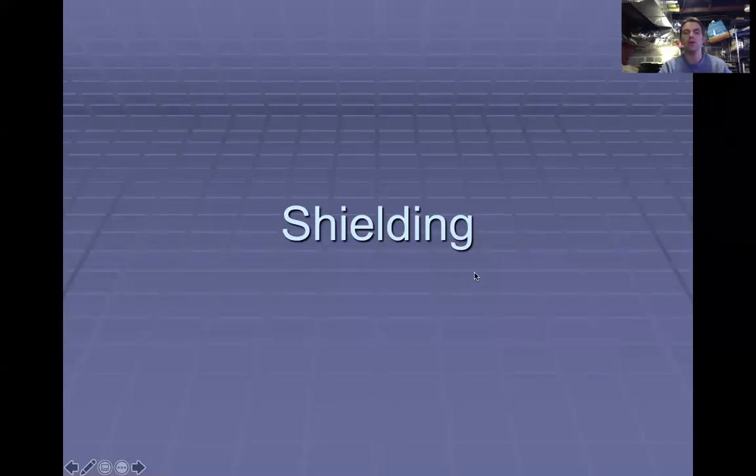Hi, everyone. The last topic we're going to cover in this entire class is shielding, which is obviously a pretty relevant topic to linear accelerators. They are probably the location with the highest intensity shielding that we have in the entire hospital. And that's just because of the amount of radiation that is produced by these LINACs, the energy of them as well, and the directional aspect, that they are very concentrated beams being pointed at these barriers.